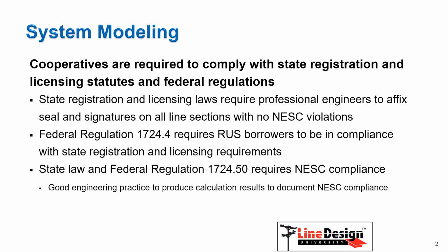Lastly, states and Federal Regulation 1724.50 require compliance with the National Electrical Safety Code. States require engineering and National Electrical Safety Code calculation results to be included in the final design submittal for a professional engineer's review and approval.